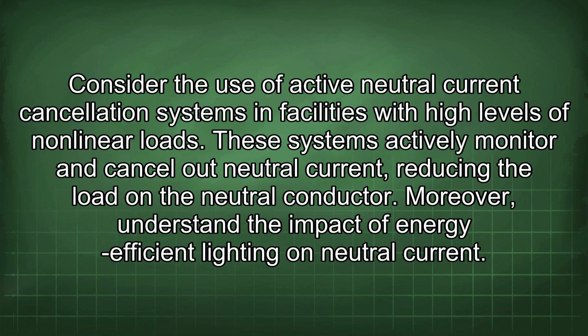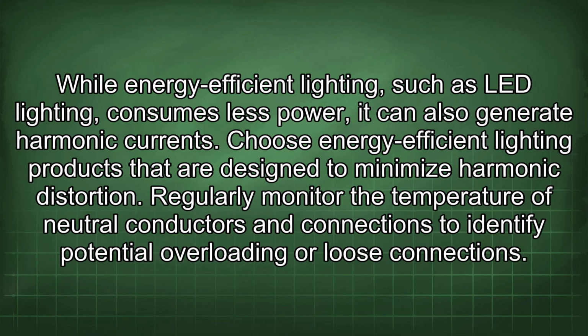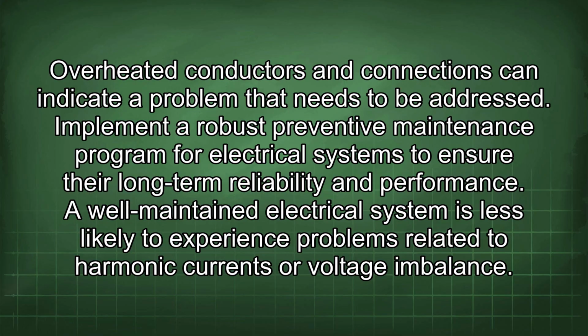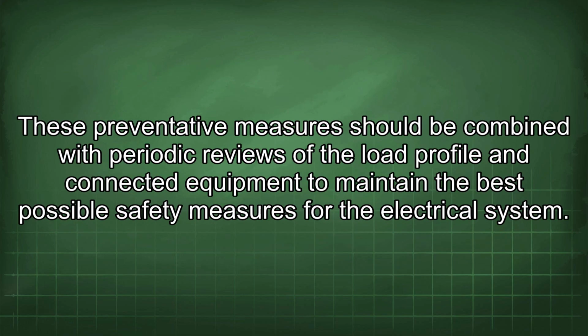Moreover, understand the impact of energy-efficient lighting on neutral current. While energy-efficient lighting, such as LED lighting, consumes less power, it can also generate harmonic currents. Choose energy-efficient lighting products that are designed to minimize harmonic distortion. Regularly monitor the temperature of neutral conductors and connections to identify potential overloading or loose connections. Overheated conductors and connections can indicate a problem that needs to be addressed. Implement a robust preventive maintenance program for electrical systems to ensure their long-term reliability and performance. A well-maintained electrical system is less likely to experience problems related to harmonic currents or voltage imbalance. These preventative measures should be combined with periodic reviews of the load profile and connected equipment to maintain the best possible safety measures for the electrical system.